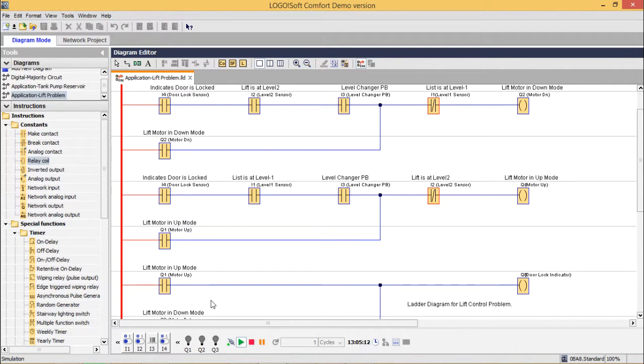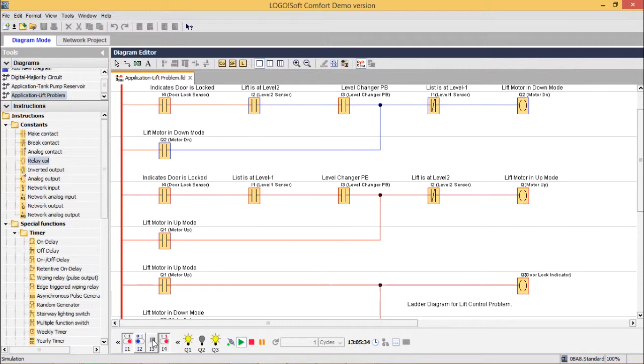In the simulation, the lift starts at the ground floor so I1 (level one sensor) is on, and the door lock sensor indicates the door is locked. No output is on initially. When the level changer push button is pressed, Q1 (motor up) and Q3 (door lock indicator) turn on. The lift moves up, releasing the level one sensor as it travels between floors, but continues upward. The lift stops when it reaches level two and the level two sensor activates.